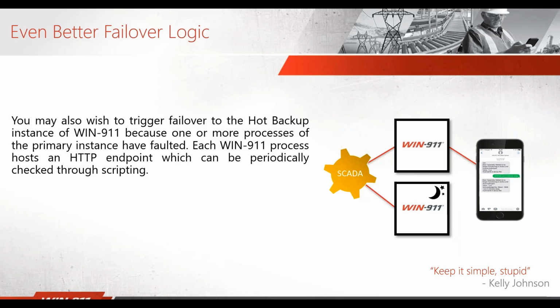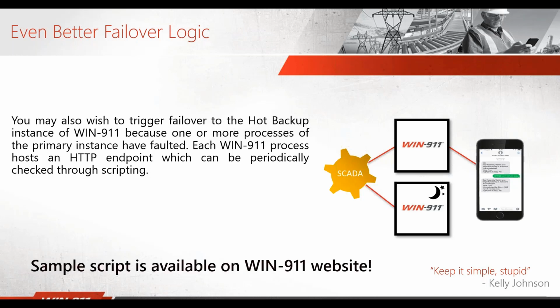So that's one way to do it. There are other ways to script your failover. Win911 consists of many processes. Each module is its own independent process, and each of these processes hosts an HTTP endpoint, which you can query to check whether they're running. We have a sample script of that on our website, so you're free to check that out. Essentially you're checking every process to see if it's responding. If it is not responding, then you can fail over to a second Win911 system so that it can take over notification for you. The sample script that we have is available in VBS form. It can easily be moved over into a VBA script if you want to run it within your SCADA system.